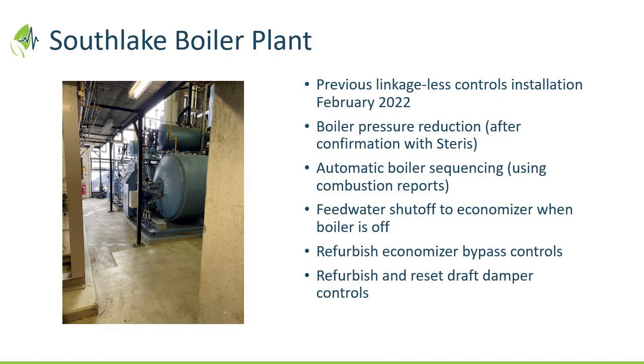And Julian, you were, yeah, go ahead, please. Thank you. My question is to Thermogenics and John, both of you. You mentioned that for the linkageless control, every 6 months you bring your contractor to do a check. Does this require a regular calibration so it'll do the job it's supposed to do, or is it annual? I'm also asking Thermogenics, because you can tell me if something is required. I have had a Thermogenics boiler before with linkageless control, but we never did the calibration. So we want to know if something is required, whether to do calibration regularly. Thank you.